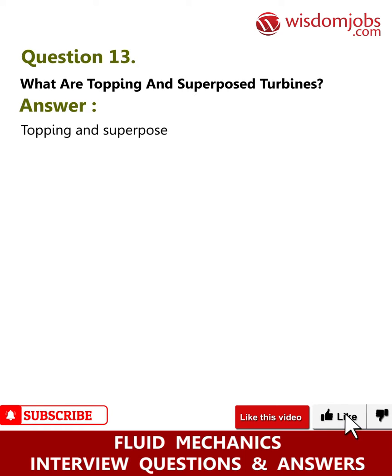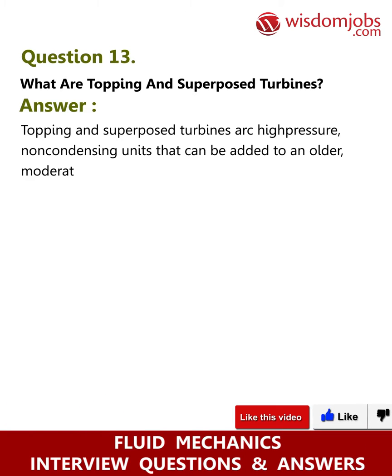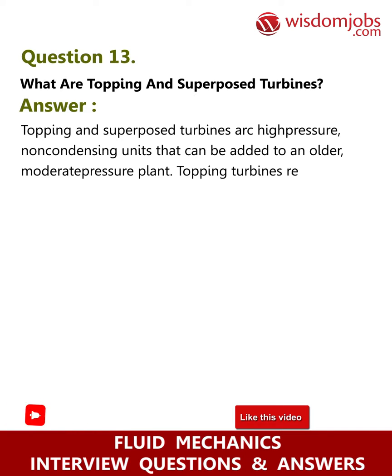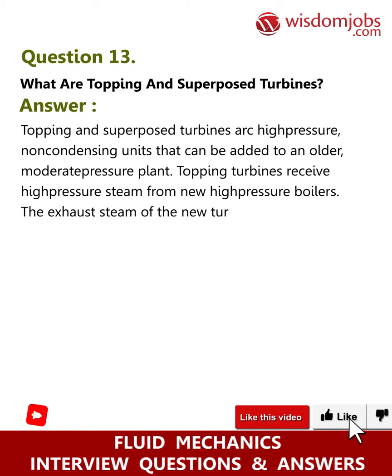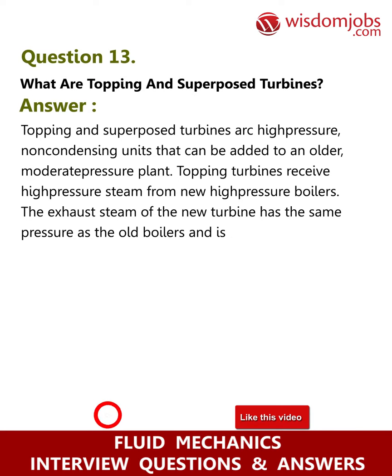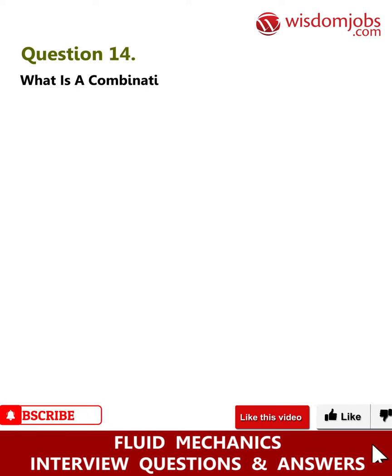Question 13: What are topping and superposed turbines? Answer: Topping and superposed turbines are high-pressure non-condensing units that can be added to an older, moderately pressured plant. Topping turbines receive high-pressure steam from new high-pressure boilers. The exhaust steam of the new turbine has the same pressure as the old boilers and is used to supply the old turbines.